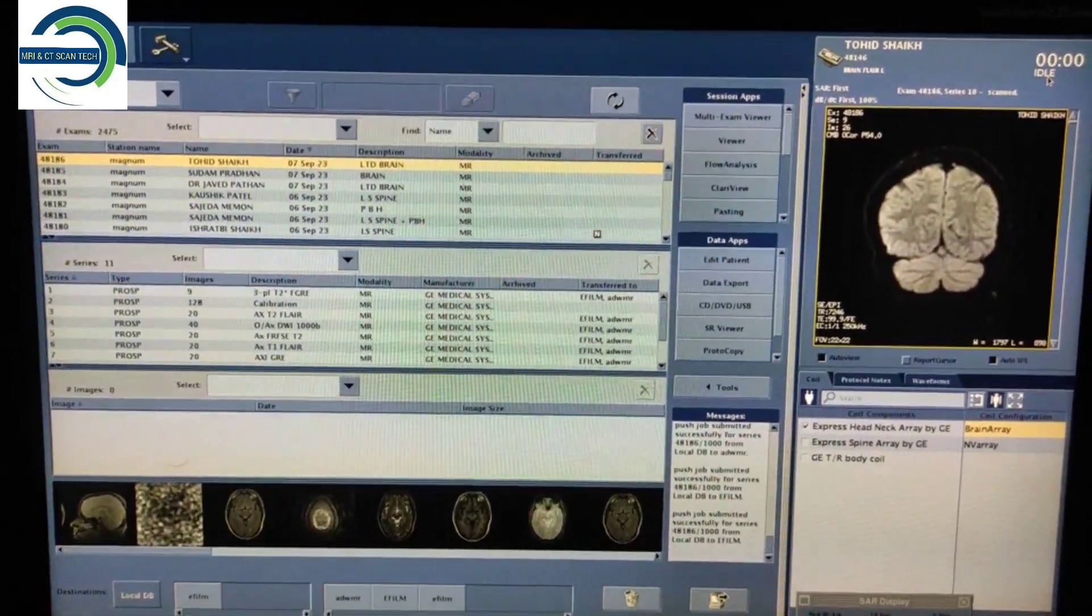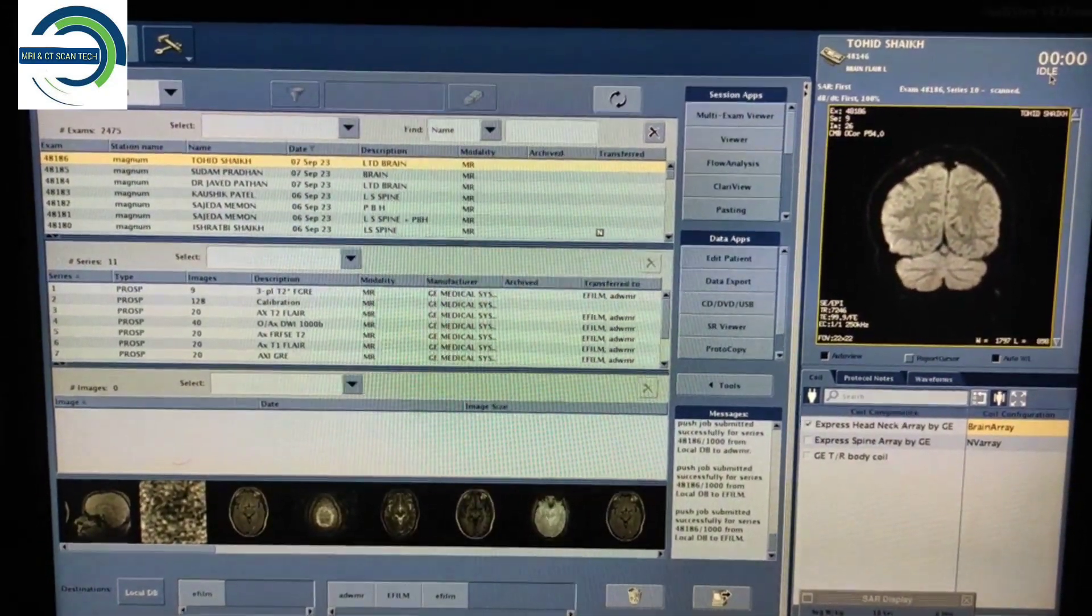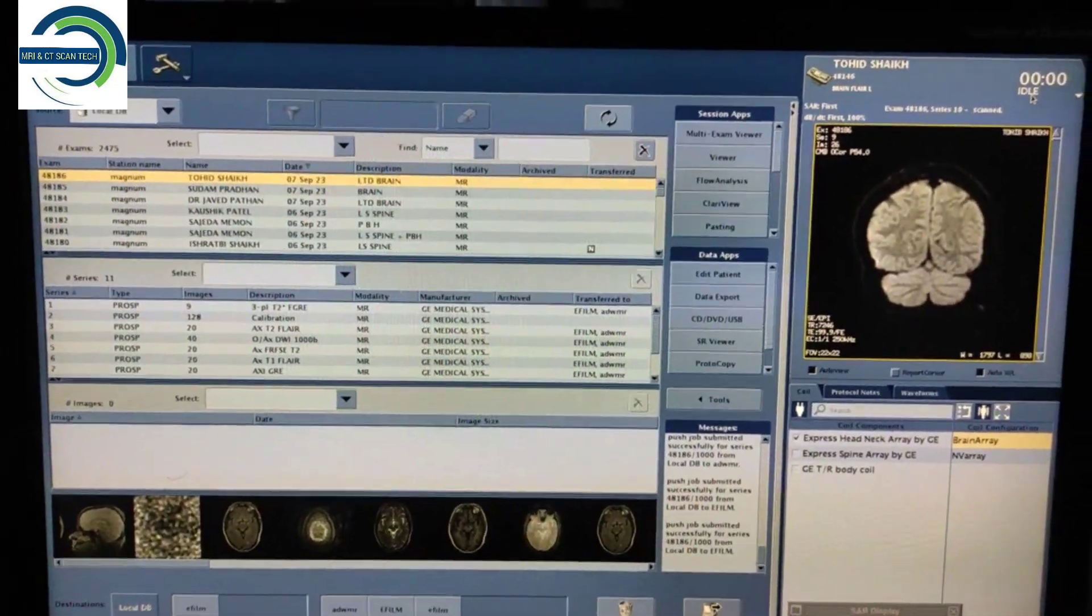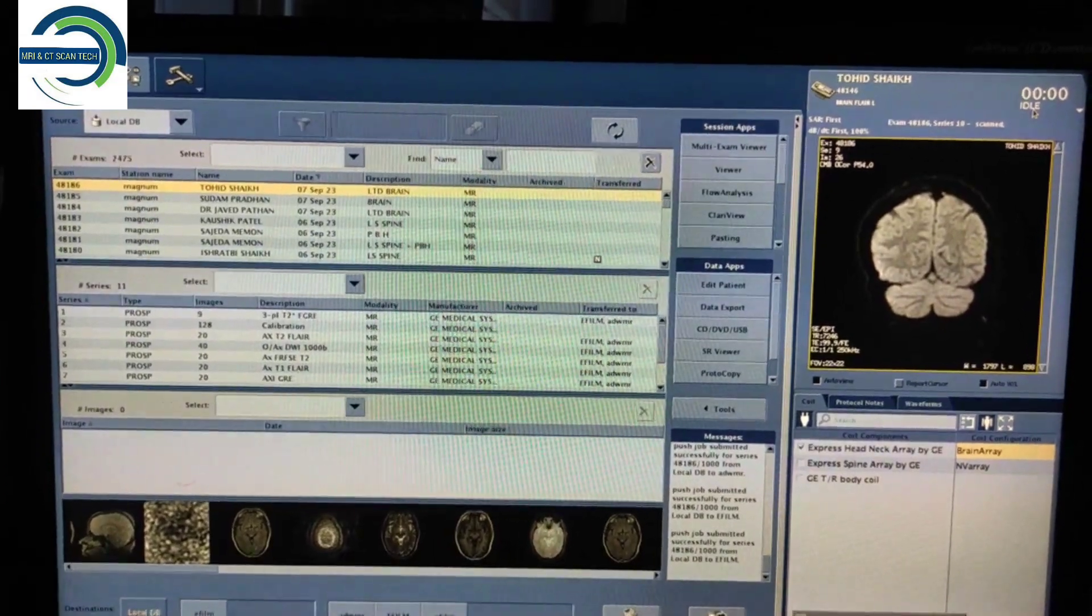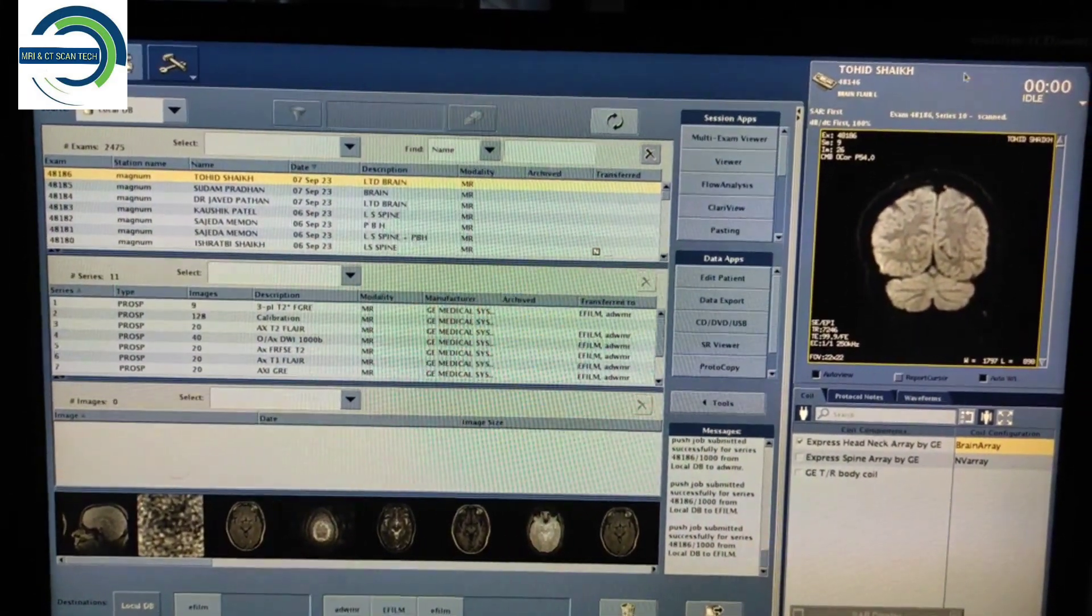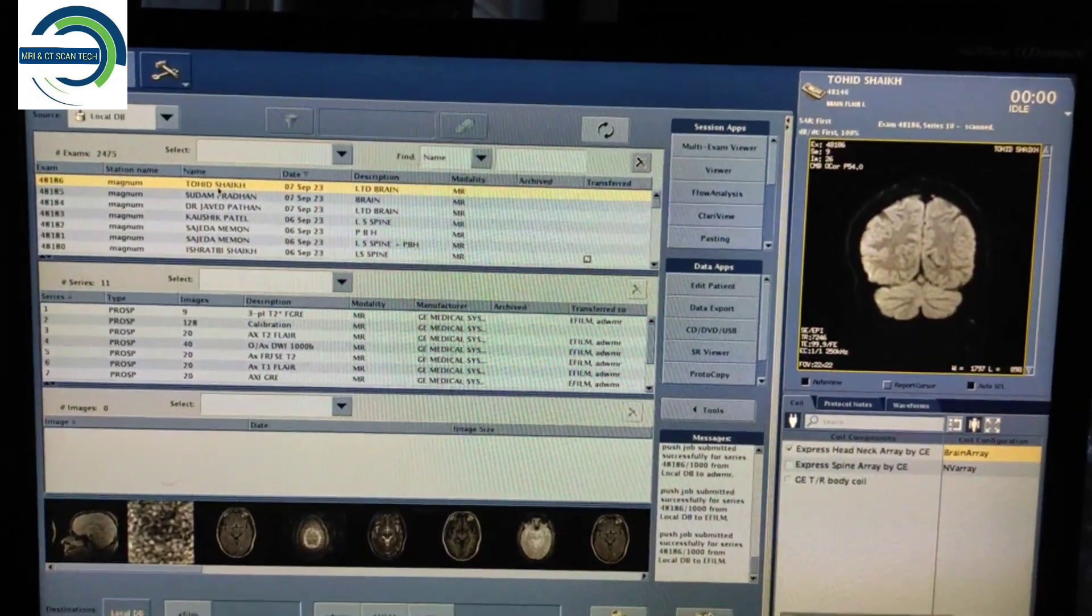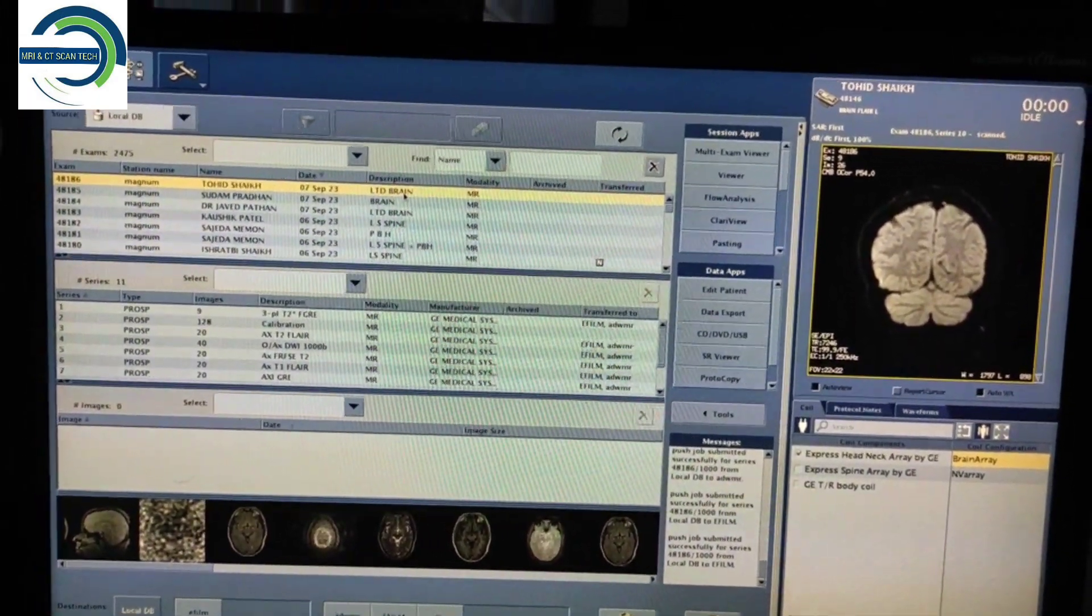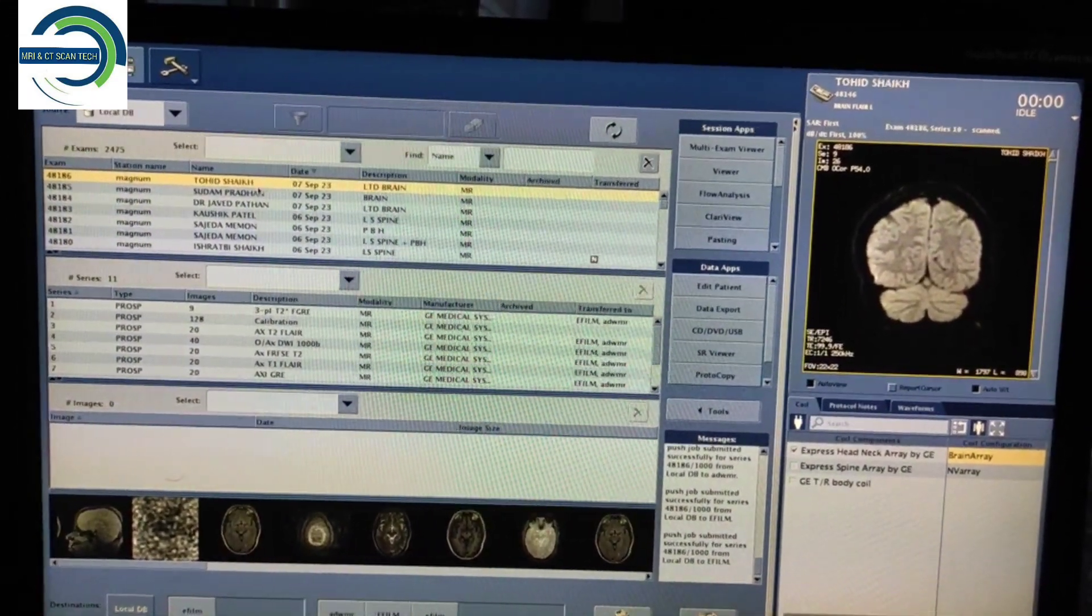Hello friends, welcome to my channel. Today I'm going to show you how to edit the patient name on GE 1.5 Tesla Brivo MR355. If you want to change the name of the patient or change the description, here's what you have to do.